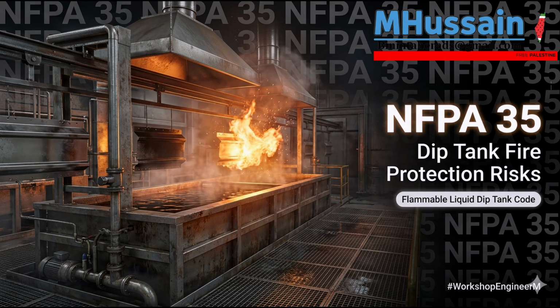Precisely. You design specific sections of the walls or roof using lightweight panels, or panels held in place by specialized low-pressure relieving fasteners. Okay. When the internal pressure from an explosion begins to spike, these specific panels blow outward almost instantly, creating a path of least resistance. Safely directing the blast. Exactly. This safely directs the immense blast wave and the fireball outside into a designated safe area, rather than allowing the pressure to build to the point where it destroys the primary structural integrity of the entire building. It's like engineering a massive pressure relief valve for a skyscraper. That's a great way to picture it.